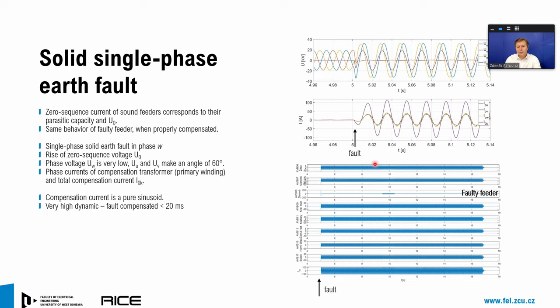Just a few waveforms. These are recordings from a solid single-phase earth fault. Here you see the phase-to-ground voltages. This is the place where the earth fault occurs. You can clearly see how the zero sequence voltage increases. This is the magenta line. And here you can see how our device immediately reacts, increasing the compensation current. The magenta one is the total compensation current, and the remaining waveforms represent the phase currents at the primary winding of the compensation transformer.